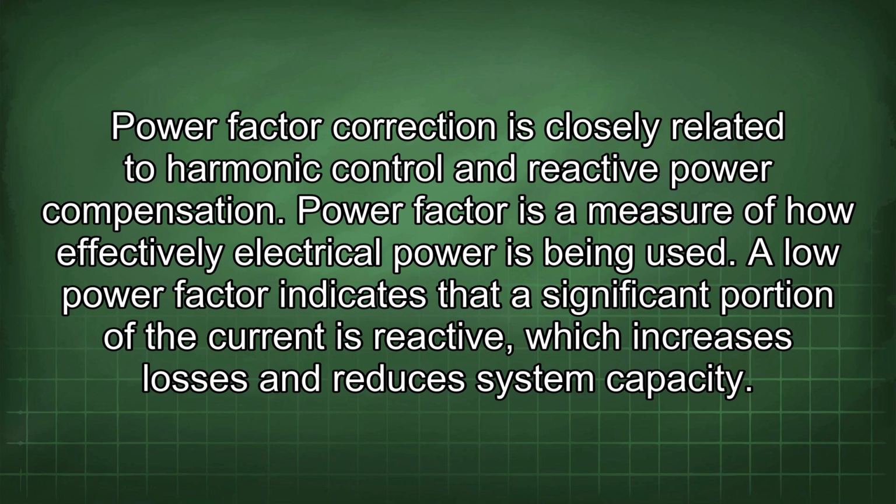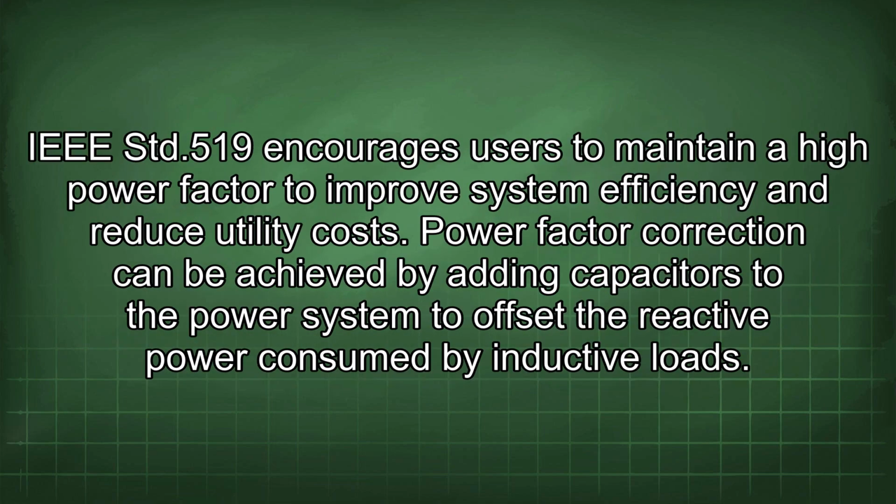Power factor correction is closely related to harmonic control and reactive power compensation. Power factor is a measure of how effectively electrical power is being used. A low power factor indicates that a significant portion of the current is reactive, which increases losses and reduces system capacity. IEEE Std.519 encourages users to maintain a high power factor to improve system efficiency and reduce utility costs.